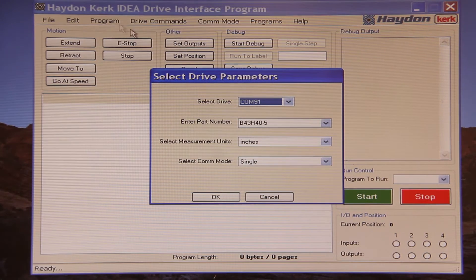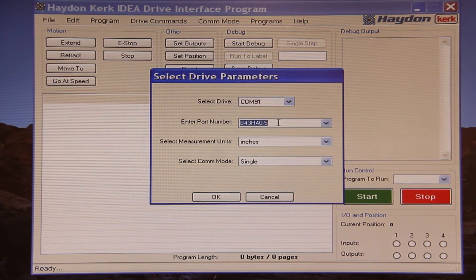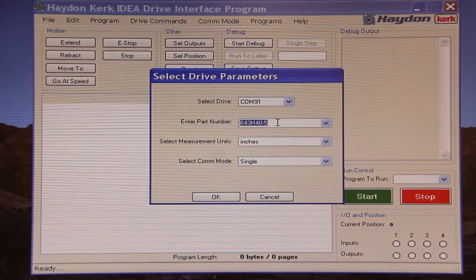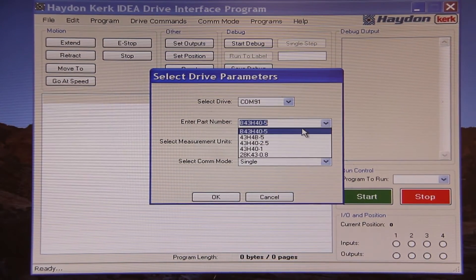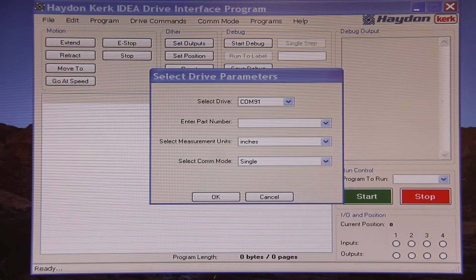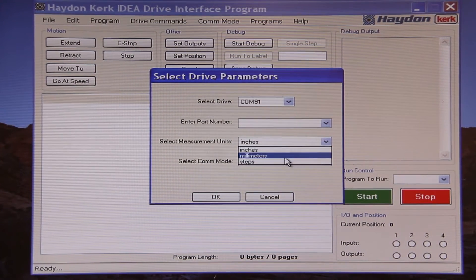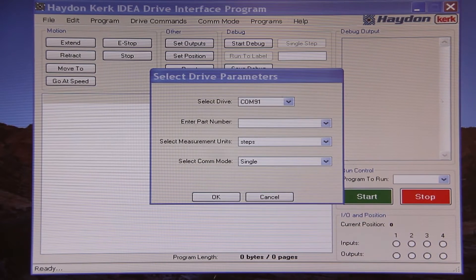On program startup the user will see the following screen. The GUI is designed with a part number system to aid the user in motor setup. This part number is for the type of motor which will be used, and the software will automatically detect which drive is connected. There are two main functions of the part number system: to limit the amount of current that the drive outputs to prevent over-driving and causing damage to the motor, and to set the resolution of the linear actuator. This allows users to not only work in units of steps but inches and millimeters as well. Avoid calculations between pulses and travel distances and work within units that you are comfortable with.